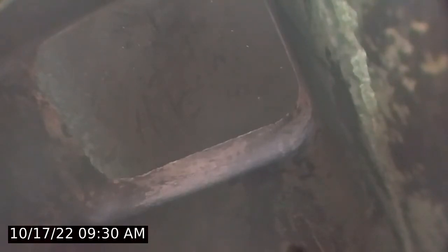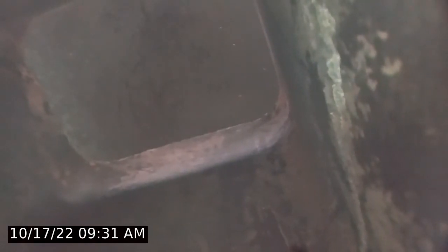I have performed a traditional cleaning with a polypropylene brush, another traditional cleaning with a stainless steel brush. We also performed a rotary cleaning along with that. Proceeding down with the camera now. Rough idea on height is just under 20 feet tall to tile.